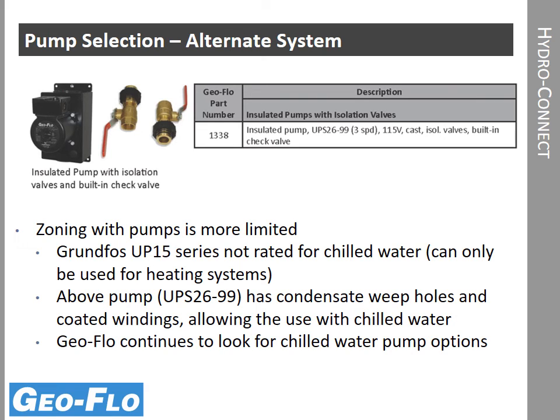Alternatively, we could certainly use pumps per zones instead of using a solenoid valve or a motorized zone valve and a variable speed pump. In this case, we do have a bit of a limitation on pumps, and that's primarily because we need to make sure that we're using a pump that's rated for chilled water. Some of the Grundfos pumps are not rated for chilled water, for example, the UP15 series. So we are offering one that will work both with hot water and chilled water. The main difference is chilled water pumps include coated windings and also weep holes for condensate. So the same pumps that we would use in the ground loop system are applicable for chilled water systems. We do have to make sure that we're using a pump that's rated accordingly versus a boiler pump, which is really not rated for chilled water. We're continuing to look at other options for the chilled water side.